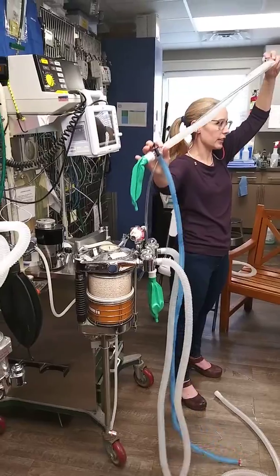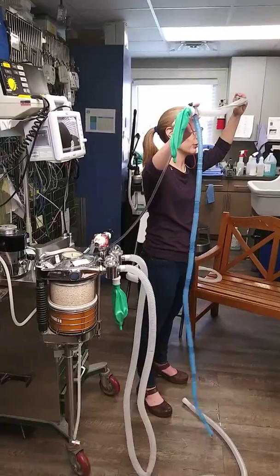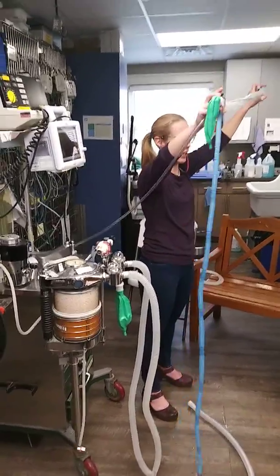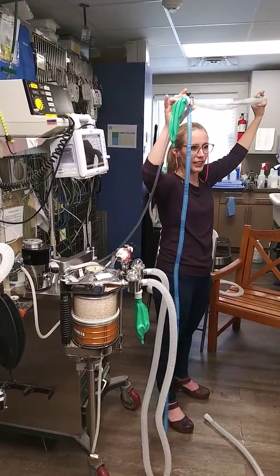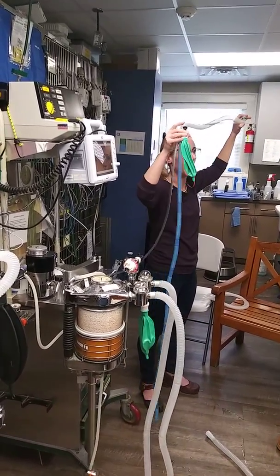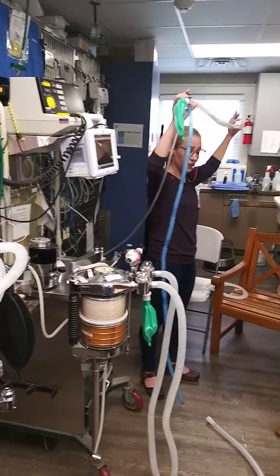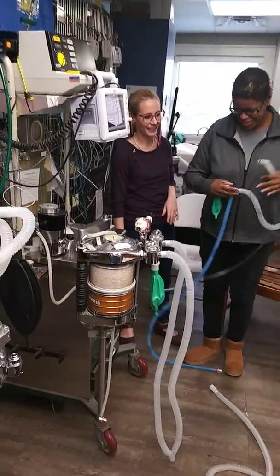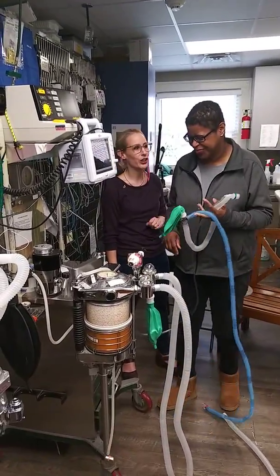All right. Joyce, I'll just pick on you since you're close enough to come up here. Would you like to trace the circuit for us? And we'll do a quick leak check. I know everyone thinks this is silly, but this is what you should be doing every time something weird happens. You should check this circuit immediately with your brain and your eyes and your hands. I mean, things go wrong, and you don't know how it got weird.